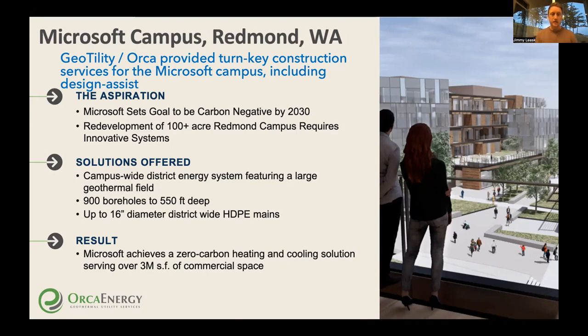Whereas campuses like this Microsoft one and others can actually share the energy, and it becomes 2 to 3 or 4 times more efficient of a system, because some areas will be calling for heating and cooling at the same time. If you have commercial space or gyms or offices mixed with residential, district energy becomes very, very efficient and popular. So you'll hear that term used quite often in our industry.